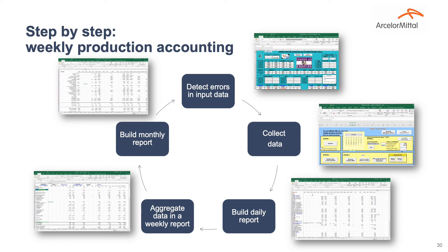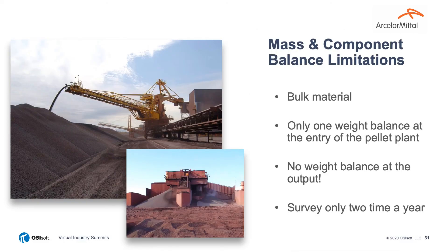The engineer also wanted a better solution. They had another big issue: bulk material means a big uncertainty. They have only one weight cell at the entry of the plant, no weight cell on the output, and inventory was measured only twice per year. With this low level of instrumentation on the main input and output, mass and component balance will increase the robustness of the model.